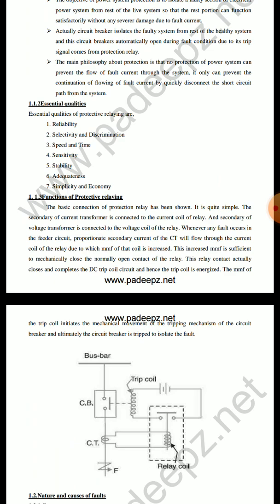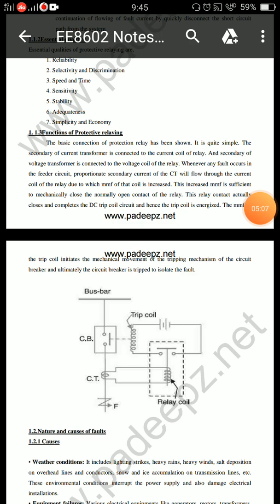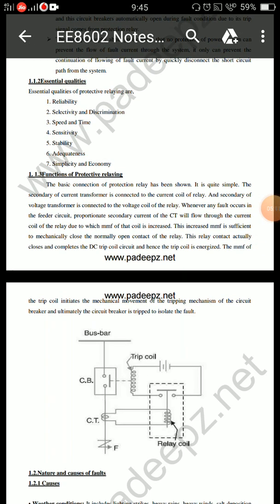We already know about these: reliability, selectivity, speed, time sensitivity, and stability. Because of the usage, cost effectiveness is needed, and for reliability, we need to use that particular setup, the trip circuit breaker and relay, accepting the size of the setup, and stability and sensitivity are needed. That particular setup needs to sense even a small error value, in a very small range. Our protection setup needs to sense that type of error also. And simplicity and economy are very important.